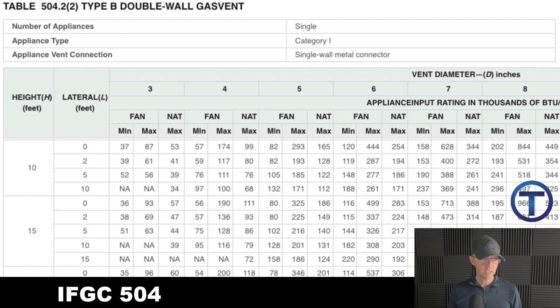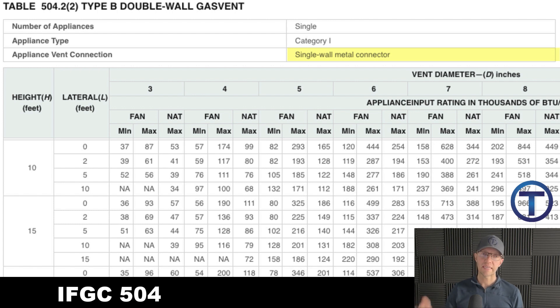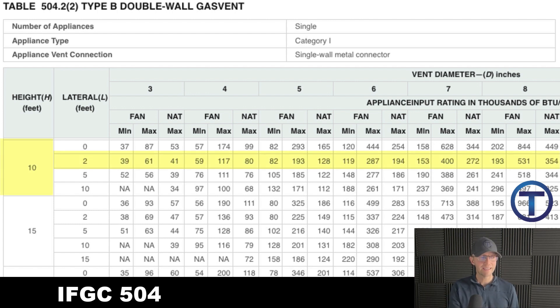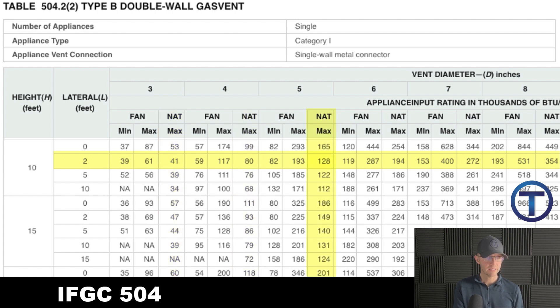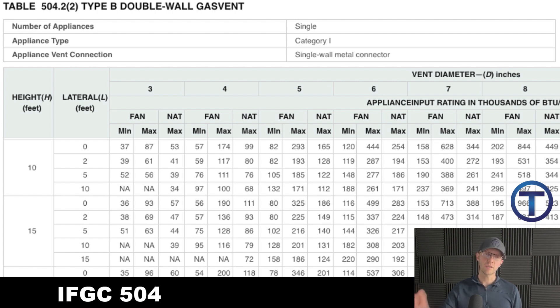Here we have it, let's go to the table. If you've been looking through, you will have found Table 504.2(2). It's the type B double wall, single appliance, Category 1. But the difference between this and the last table is the single wall metal connector — so we're going to run our single wall over to that B vent. We were dealing with a height of 10 feet, lateral was two feet, so that puts me right into this row. We had 120 BTUs and natural draft. Coming across and looking at my natural draft columns for 120 — it's going to be more than 41, more than 80, and less than 128, so I can stay in this column, head up to the top. Once again, the vent needs to be a five-inch pipe. Hopefully that's what you discovered — Table 504.2(2), five-inch pipe.